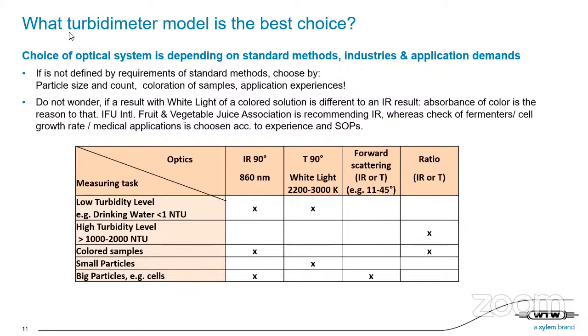But if you're not measuring in water, you can choose the best instrument for your application. And if it's not defined by either, for example, breweries or water regulations or whatever, then we come to the standard operation procedures of a company. And then here you have a choice, which means IR is very good in low-level turbidity. For high turbidity levels, ratio is at a certain point a must. Colored samples, the impact of color, can be excluded with IR or with ratio as well. Small particles are better measured with white light due to the relation of the scattering effect with a small particle at smaller wavelengths. And big particles can, for example, be measured better either with IR or with brewery-specific, for example, 11-degree forward scattering.